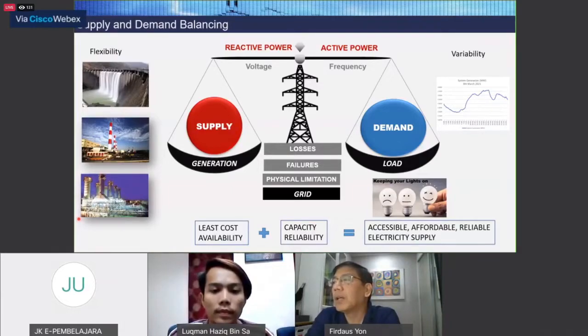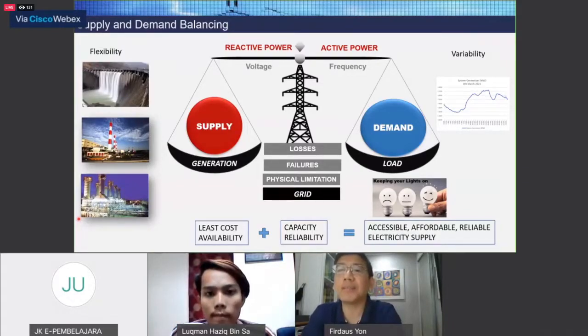Now it is also about managing and balancing the reactive power and active power. Active power is actually the megawatts, reactive power is actually the megavar. The useful energy is actually the active power, that is where we bill you for using. That's what drives machines and stuff like that. But the system requires reactive power, primarily to provide the magnetic field for the generators, otherwise they can't produce electricity. So basically it's also to produce the voltage that will drive the current.